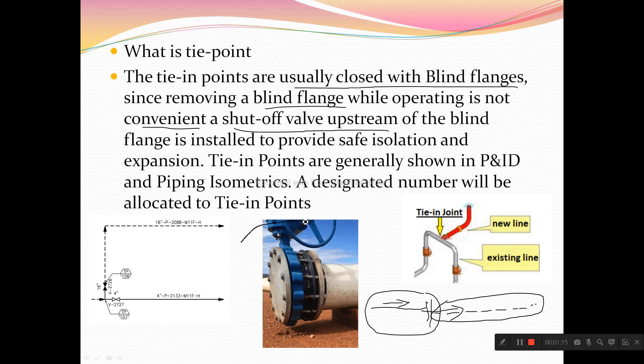That's why we are using a shutoff valve upstream of the blind flange. Wherever you are getting a tie point, you cannot just replace the blind flange and connect a new line. The flow should be stopped first, and then you can remove the blind flange and connect with the new line.